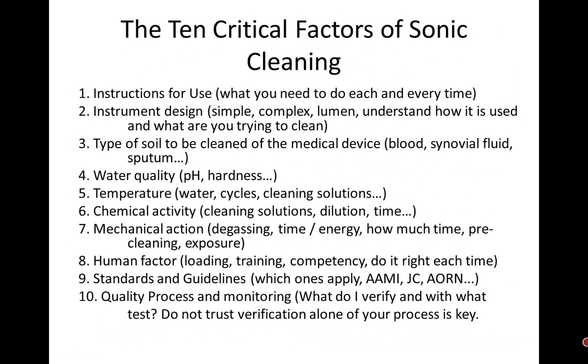The water hardness. If the water is too hard, you will use more detergent. What is the pH level? If it's stable, good water quality coming in. The temperature. What is the temperature that you are going to be using? Is it at the right temperature, both for your cleaning solution? A cleaning solution, if you're using a protease detergent and you're putting orthopedic instruments in there that have synovial fluid, they themselves will not get it as clean as it's supposed to. So that is all very important.